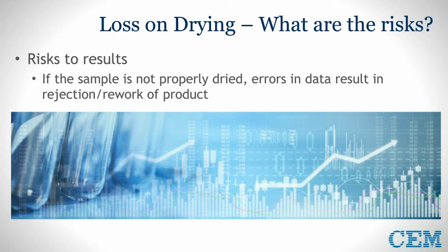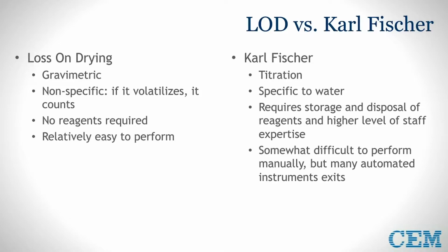So let's talk about the difference between loss on drying and Karl Fischer. I seem to get this question quite a bit from customers who ask if loss on drying is a good replacement for their Karl Fischer. These are both very important tests, and they both serve different functions, so we can discuss here what those differences are. Loss on drying is a gravimetric test.